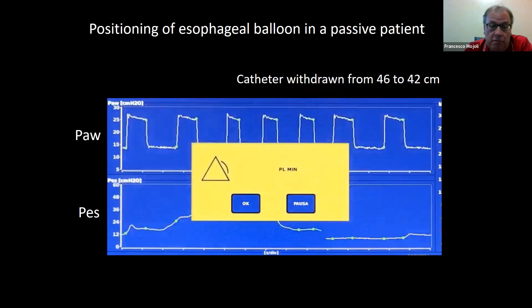So we have to withdraw the catheter again by another 4 centimeters. You see that as soon as you move the balloon, there is a big reaction from the patient, or let's say the esophagus. There is some swallowing. You have to wait for normalization and stabilization of the pressure. But now you see there is clearly a change, because the baseline level of balloon pressure is no more 8 centimeters of water, but is close to 15 centimeters of water. So probably we entered the thorax with the balloon. And you also can see that the heart noise is more clear now.